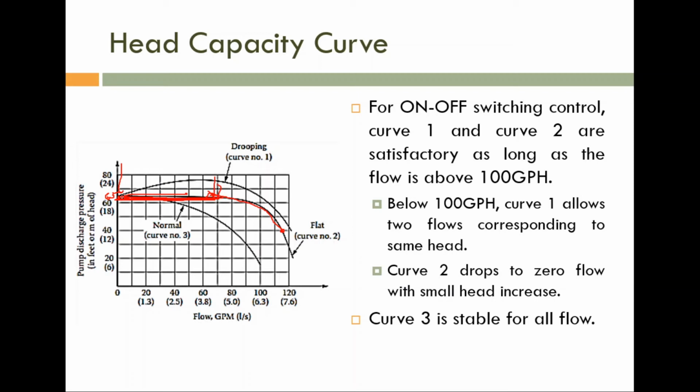That is happening if you are using a flat pump. So normally, for normal applications, we need to use a pump with a normal curve. What is the advantage of the normal curve? This is always stable. It is providing a stable flow. For all flow rates, this one is stable. The operating condition is stable. So that one is the advantage of the normal curve.